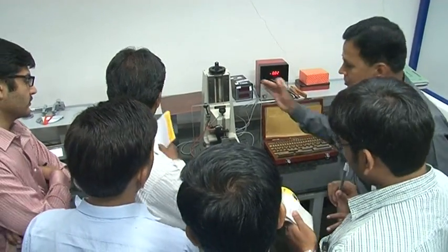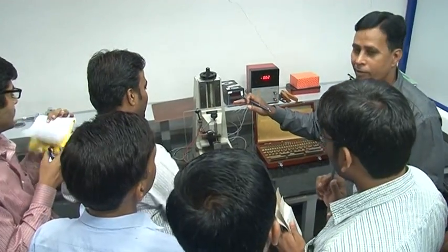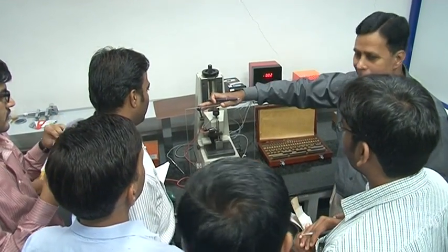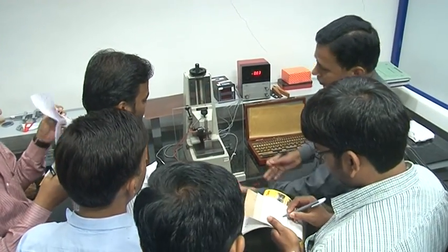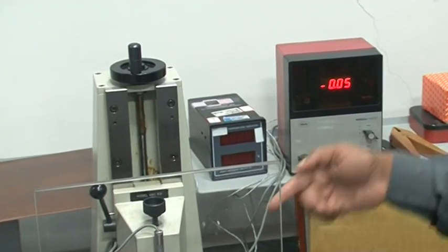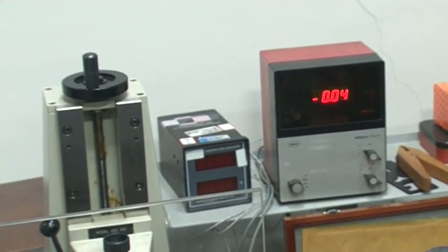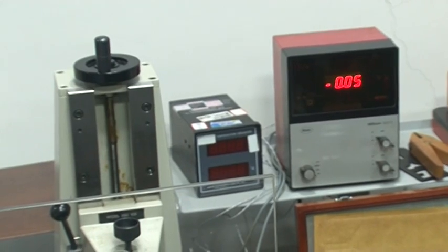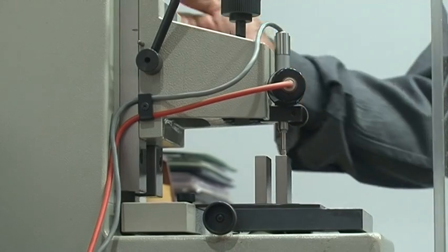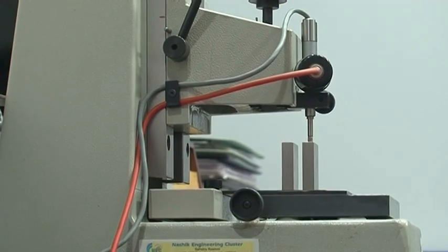We use this set as a master for calibrating gauge block sets of 0 grade and onward. First the master gauge block is placed in the back side socket. Then the gauge block to be calibrated is placed in the front side socket. The reference value of the master, that is the deviation observed during calibration, is set on the DRO and then the reading on the gauge block to be calibrated is taken.